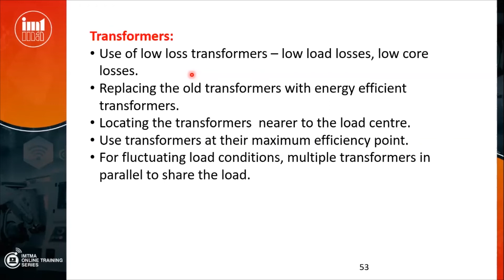For fluctuating load conditions, use multiple transformers in parallel to share the load. There are presses and forges, places with fluctuating loads and impact loads. It is better to segregate them and have a different transformer. Instead of one 500 kVA transformer, have two 250 kVA, or two 300 and 200 kVA.